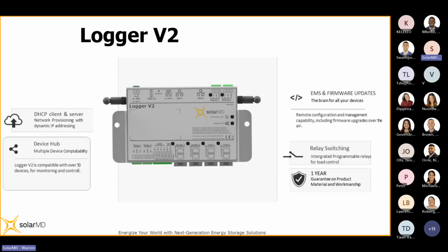Once the logger is up and running, it will broadcast its own Wi-Fi signal to which you can connect your laptop or smartphone, and then begin configuring the logger to connect to the customer's Wi-Fi network, or make the necessary changes to add and remove Solar MD devices and inverters. So it's much like a Wi-Fi repeater: it broadcasts its own signal, you connect to it, tell it what Wi-Fi network it must connect to, it associates, and then the logger will be accessible as it connects to our cloud service.